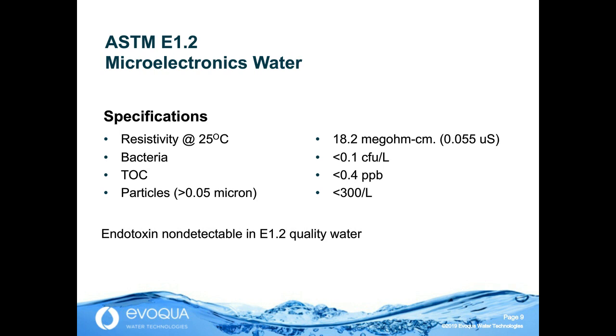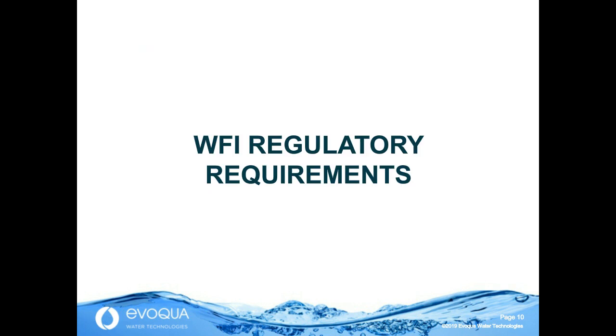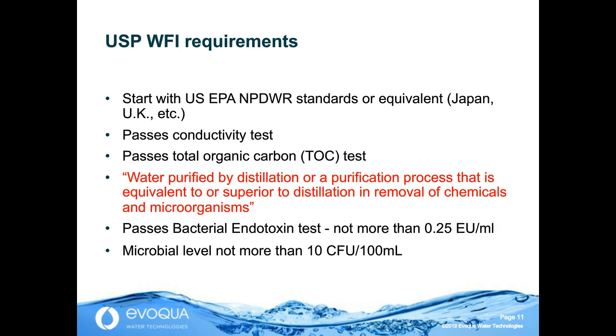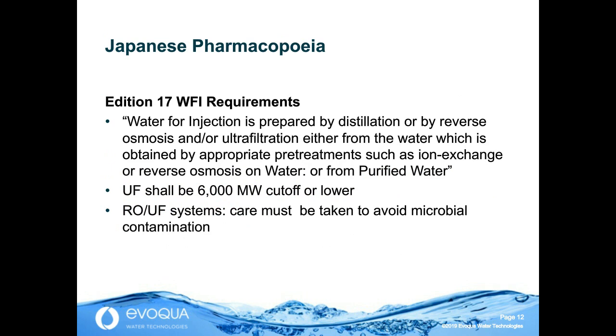So let's take a quick look at regulatory requirements. In the U.S., that in red, water produced by distillation or a process that's equivalent or superior to distillation in removal of chemicals and microorganisms, therefore no process restrictions, open to all. If we look at the Japanese pharmacopoeia, it is again distillation to compare with, or by reverse osmosis and/or ultrafiltration produced from water, which is their drinking water equivalent, or from purified water. So it could be purified water by ion exchange and then followed by ultrafiltration. So here we see both membranes mentioned, reverse osmosis and ultrafiltration, but not a strict requirement to use both.